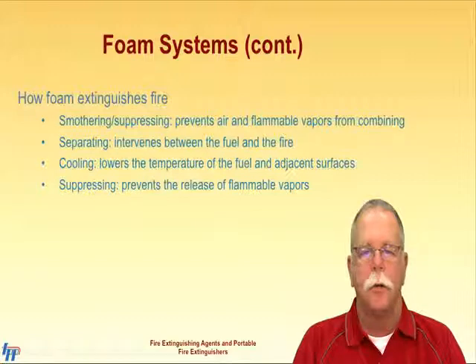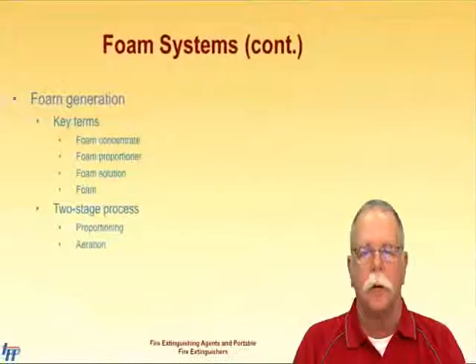To generate foam, 4 components are needed, which has come to be known as the foam tetrahedron: foam concentrate, water, air, and mechanical agitation. Once all 4 components are present, generating foam is a 2-stage process. The first is mixing foam concentrate with water in the correct ratio, which is called proportioning. The second stage is to generate bubbles by mixing air with the solution during mechanical agitation. This is called aeration.